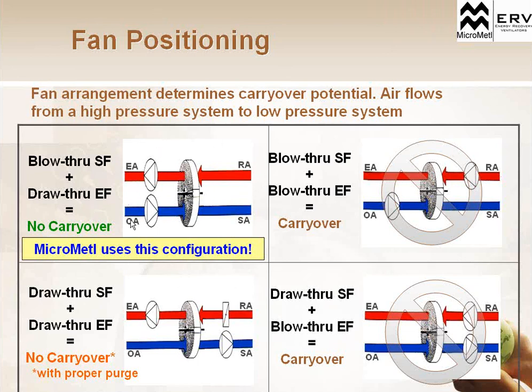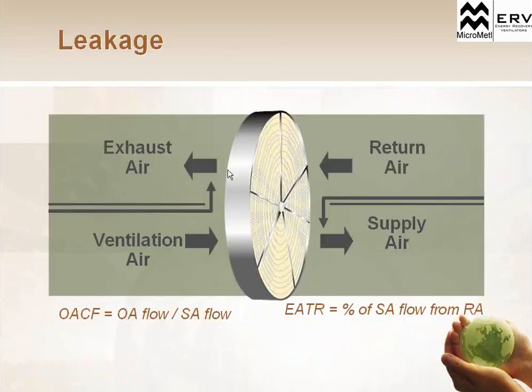So there's a specific design to the motor inside the energy recovery unit system. And whereas we said an inline design, an ERV is usually a packaged piece of equipment, but doesn't always need to be. Commonly with air handlers, we're using energy recovery devices or heat exchangers in line with an air handler. So sometimes with these blowers, we need to be aware of how we're pushing and pulling the air over that energy recovery system.